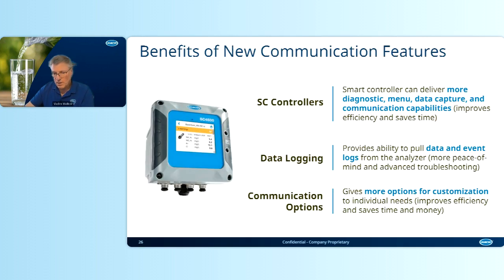Now, the controller. This controller also provides a smart version with connectivity to the cloud. However, the internal functions such as diagnostics, improved menus, and data capture and logging features provide additional capabilities. And the communication capabilities, externally and internally, improve efficiency and save a lot of time and money. We have multiple communication options, the protocols to connect the instruments and sensors to outside devices such as SCADA or DCS systems, and that is all provided by the SC controller, and the SC4500 is represented here as the latest representative of the Hach SC family of controllers.